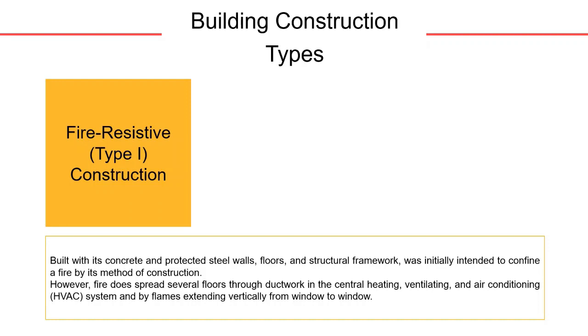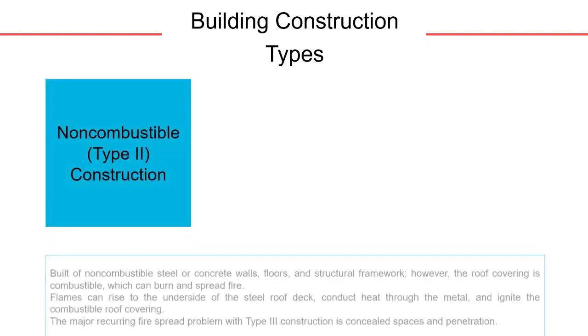The vertical spread of flames from windows below to windows above is another way of fire spread throughout a Type 1 building. Flames erupting out of a heat-shattered window can break or melt glass in a window directly above. Once the window above is open, flames can enter and ignite combustible ceiling tile, wall hangings, or furnishings. Even if the windows do not melt or break from heat, concealed cavities between the exterior wall and the end of the floor slab can allow the vertical spread of fire and smoke from floor to floor above and near a window.